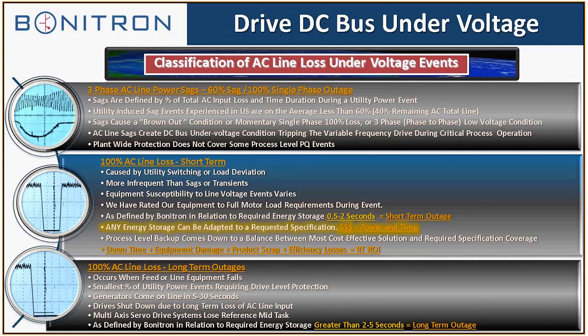Usually in a lot of cases with a full AC line loss, it can turn into a long-term outage, and that's where you bring the generator up, and we usually bridge the gap between AC line loss and gen set up. We usually rate our equipment to the full motor load requirement during an event, because we're providing everything to the drive for that period of time. When the AC line comes back, the DC bus comes back, and then the ride-through shuts down and waits in a static state. Now, as far as these terms out there in industry, Bonitron has developed these categories due to the energy storage capabilities. So we've matched up the energy storage, we've defined the percentage of events, and that's where we come up with all three of these categories.